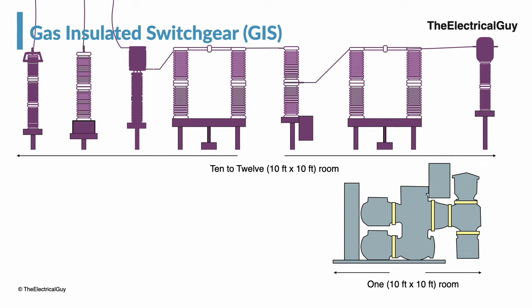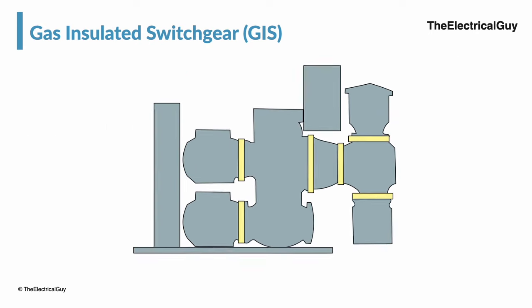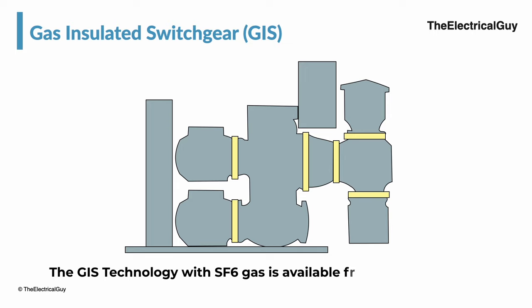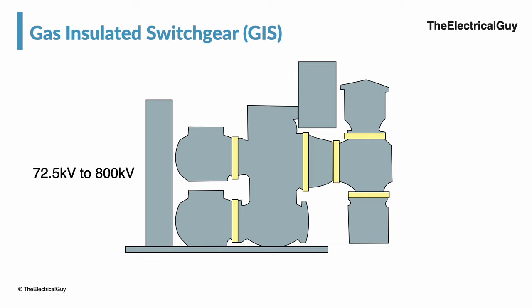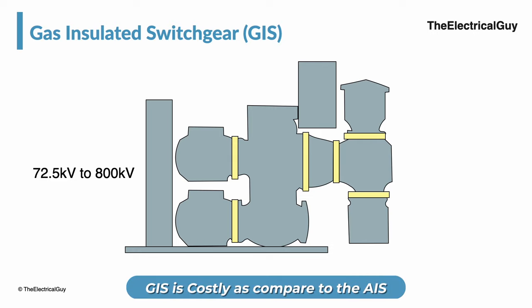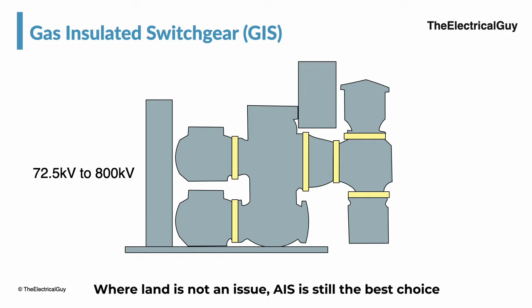GIS technology is not new — it has been available for more than 30 to 40 years. The GIS technology with SF6 gas is available from 72.5 kV up to 800 kV. This technology is preferred where space limitations exist, for example when building a substation in a densely populated city. However, this technology is much more costly compared to AIS, so in many cases where land is not an issue, AIS is still the best choice.